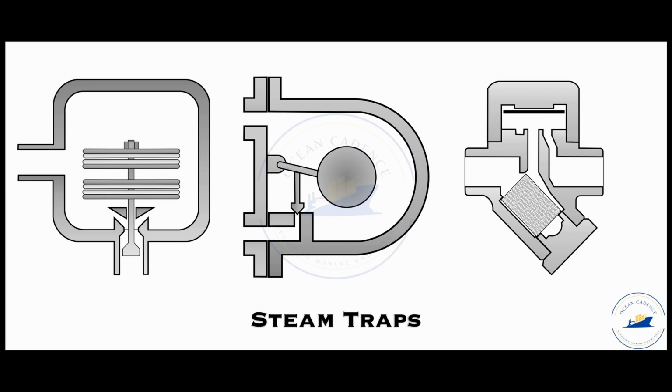So the proper functioning of a steam trap is extremely important to make sure that live steam in its pure form does not escape the circulation circuit and reach the condensate circuit, as it will create a lot of haphazard phenomena not only in the line but also in the afterward devices, and the circulation line temperature will also go higher, whereas the heat loss from the steam line into the adjacent chambers would not be sufficient, so the heating of large volumes such as the bunker tanks or freshwater tanks would not be done at optimum efficiency.